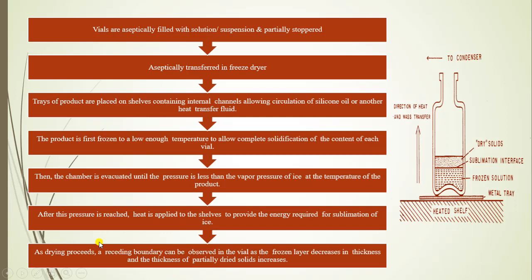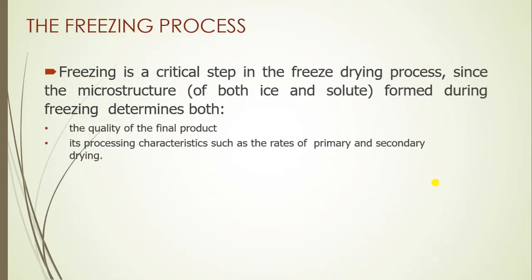Once this pressure is reached, heat is supplied to the shelf to provide the energy required for sublimation of the ice. As drying proceeds, a receding boundary can be observed in the vial as the frozen layer decreases in thickness and the thickness of the partially dried solid increases. Eventually, the preparation will be completely dry.